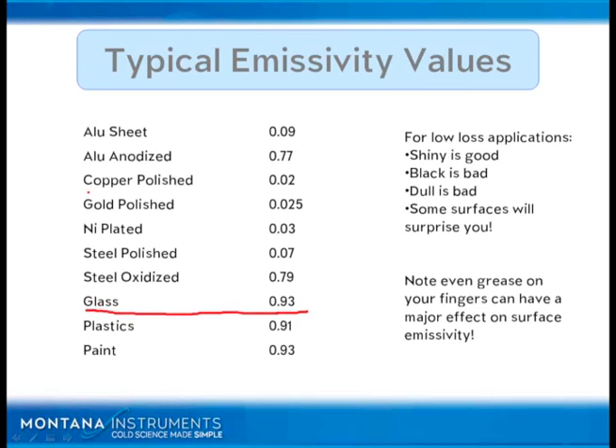Notice as a point of comparison, if you have a nice polished copper, it's 0.02. This would be assuming that it's shiny. If it's dull because it has some oxidation on it, or the surfaces are rough, and also if it has oil or finger oils or grease on it, this actually adds to the emissivity.